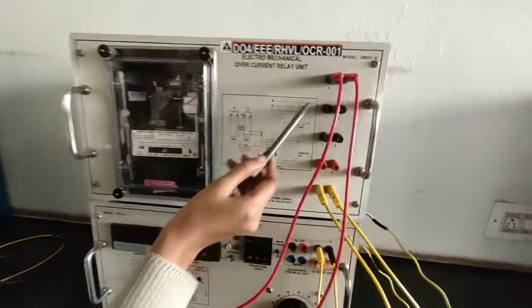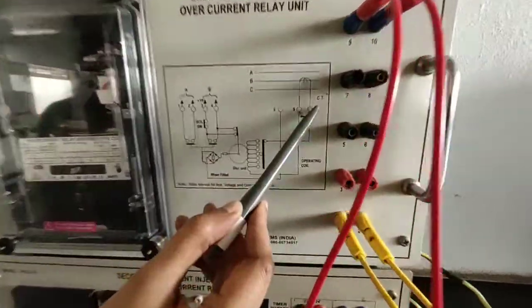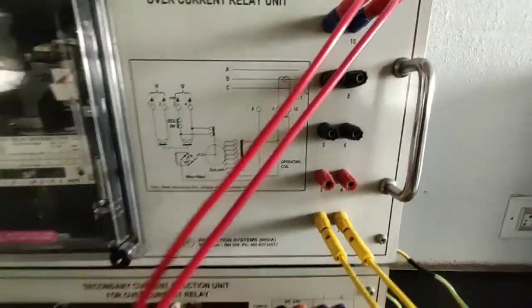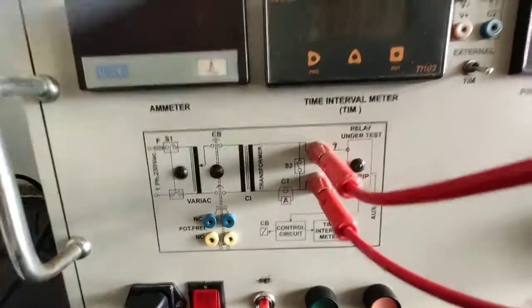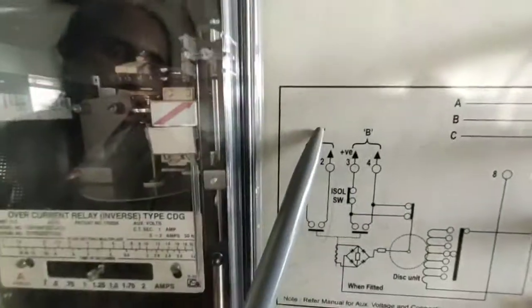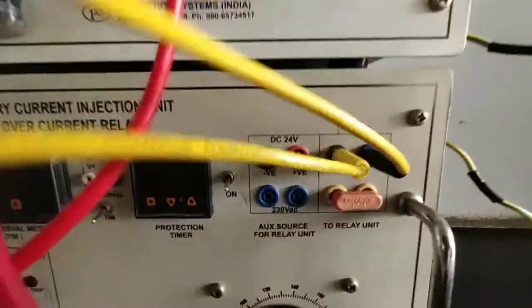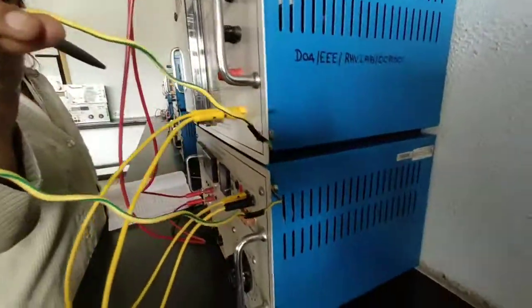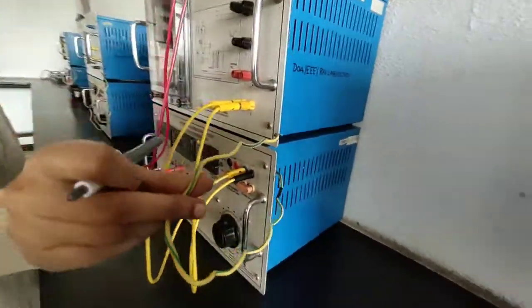The connections are, we are using the current transformer for the overcurrent relay. For that reason, 9 and 10 are connected to the CT terminals. This is 9 and 10, connected through the CT terminals. And then you can see 1 and 2 are connected for alarm or IA. So 1 and 2 should go to the NO port. NC is shorted, and ensure that both the kits are grounded. In all the setups it will be like this only; if not, an extra ground button will be there.